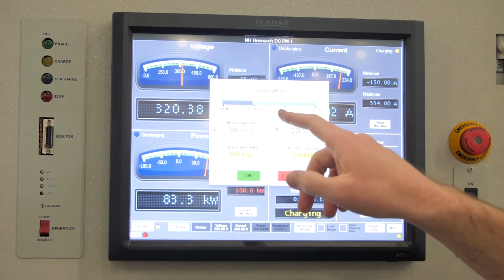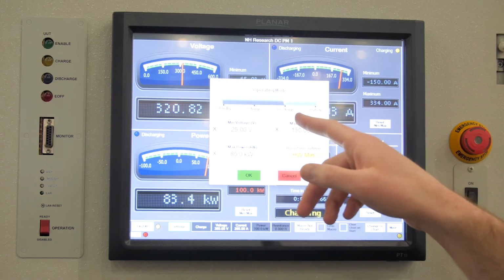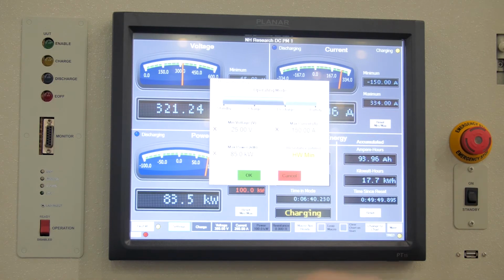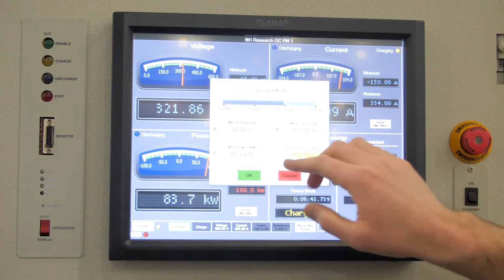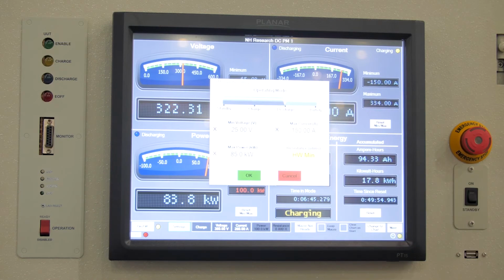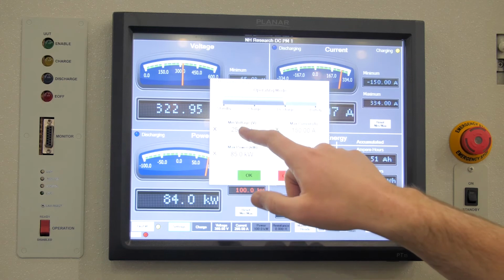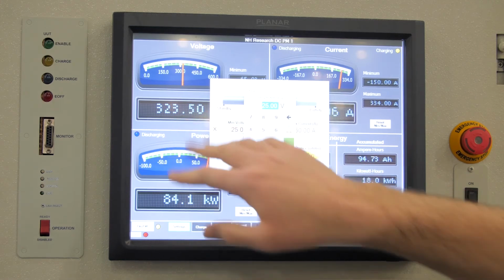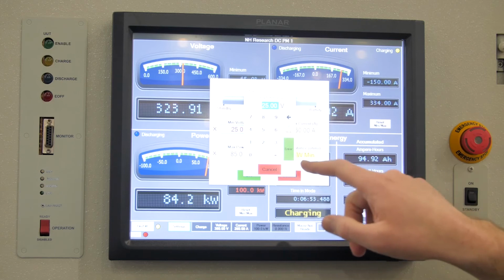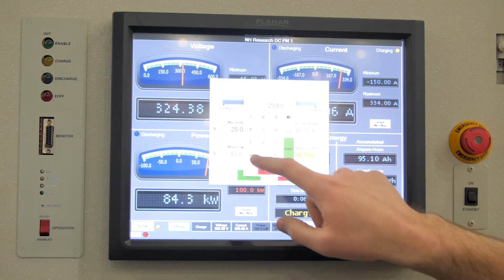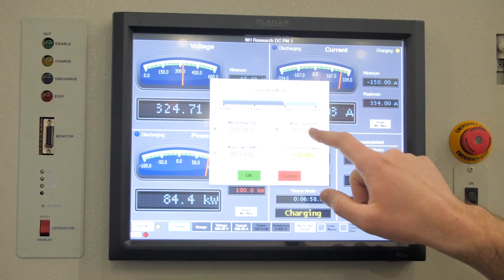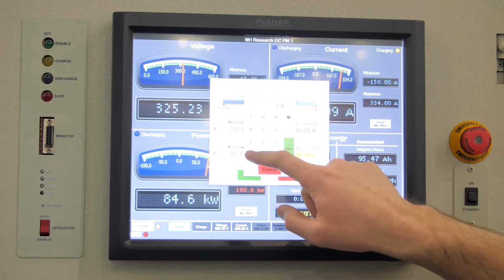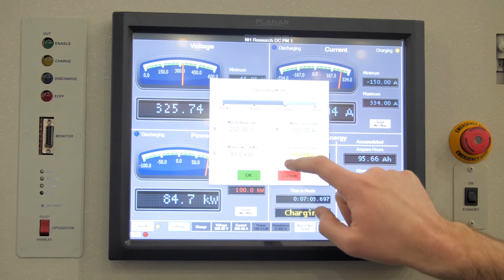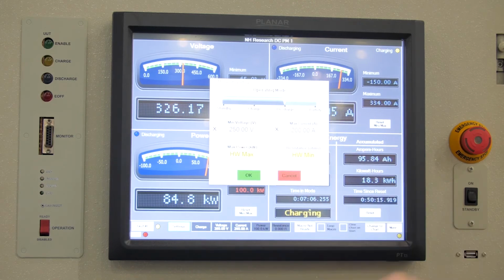If we wanted to, say, switch into a discharge, right now we're, again, charging, you can do a constant voltage, current, power, or resistance, or you can do any combination of the four. So in this case, right now you see we're at a voltage of about 320 volts. We can switch and move into a discharge to come down to, say, 250 volts. You can set your max current. We'll just say 200 amps for fun for the moment. And then we can max out our power and minimize our resistance to just do the most that the system's capable of. Again, in this case, 100 kilowatts would be your maximum power.